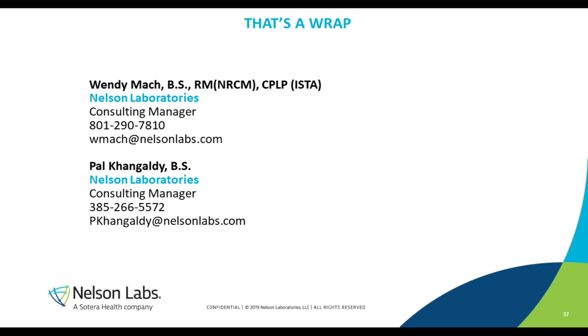I would say no, because at that point, you're specifically looking for the dye to flow through the seal via a channel. If the dye was migrating and not through a channel, it would be considered wicking. That's another phenomenon you have to be very aware of when you're dealing with the dye migration test, because the current recipes allow for wicking within 5 seconds. So there is a time limit on how long you let the dye set against the seals, and it becomes very difficult after that to identify true failures from false failures because of the wicking of the fluid through the porous material.